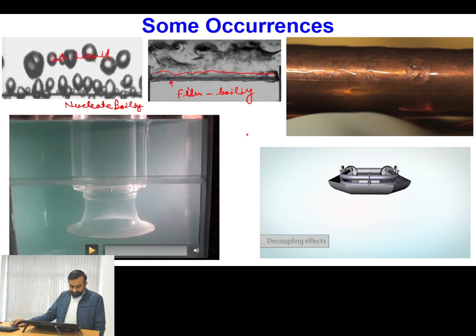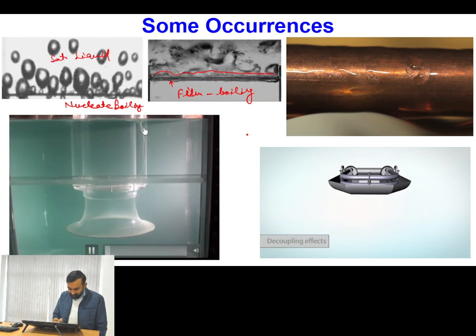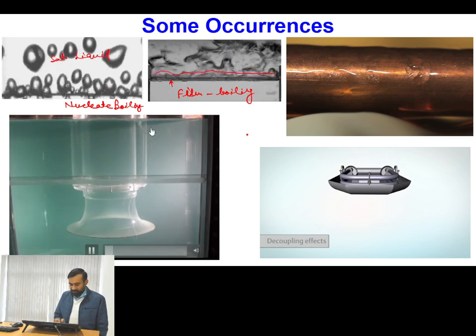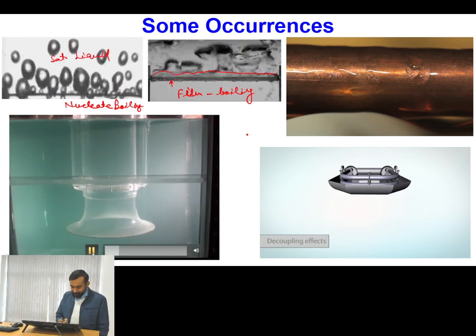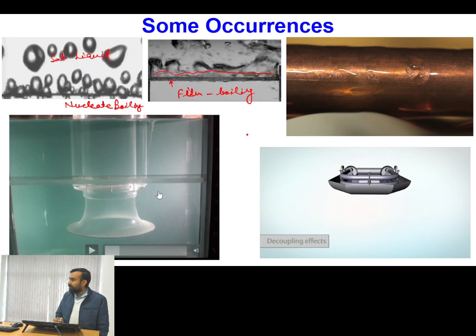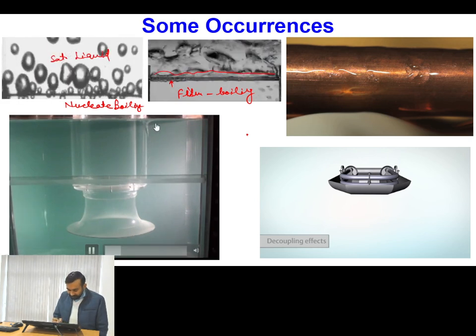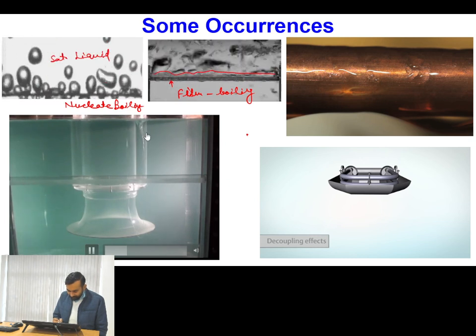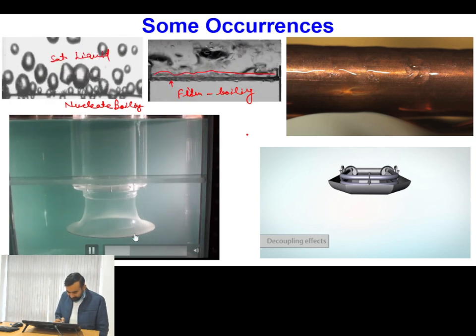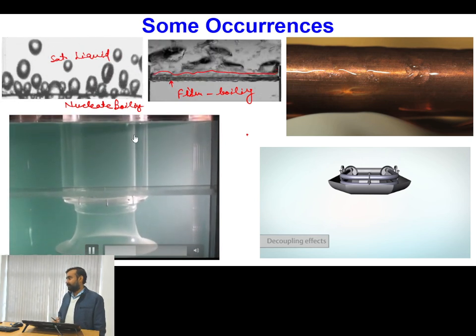Next you can see this is a typical application. From here can you see what is happening? So this is a tank, and this is the intake of a pump which is taking water from this tank. Now you can see here this small amount of air is entering, and this air thread is actually being extended even into the intake. Okay.